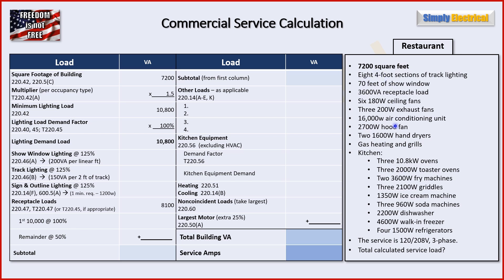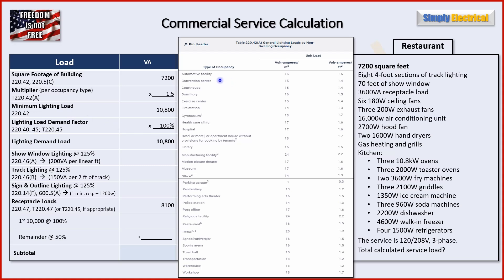We have all our data and we're going to start plugging it into our chart. We start on the left by getting the square footage — we are told we have 7,200 square feet, so we plug that in. Then we need our multiplier from Table 220.42A, which lists different occupancy types and gives a volt-amp per square foot on the right. We go down to restaurant and get 1.5 as our multiplier. So 7,200 times 1.5 is 10,800 VA — that gives us our minimum lighting load.